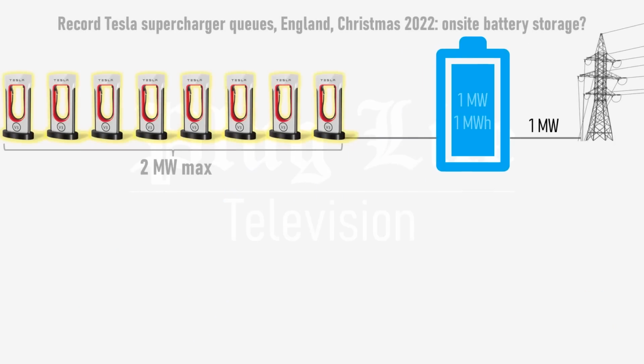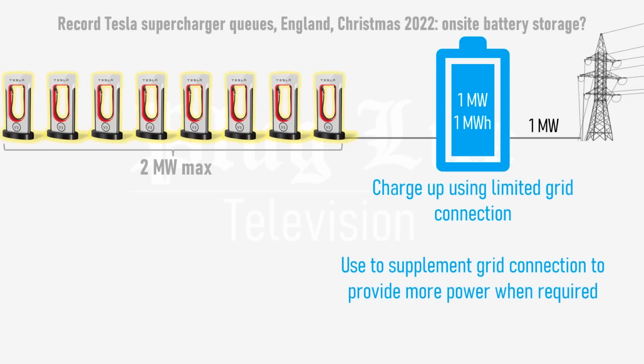A battery installed between the chargers and the grid connection can be charged up using whatever grid capacity is available, then combine its discharge power with the grid connection to supply more power to the chargers than the grid could do on its own. Take for example a 1 megawatt grid connection and a battery that can discharge at 1 megawatt. That would give enough power to supply 8 V3 Tesla superchargers at once.